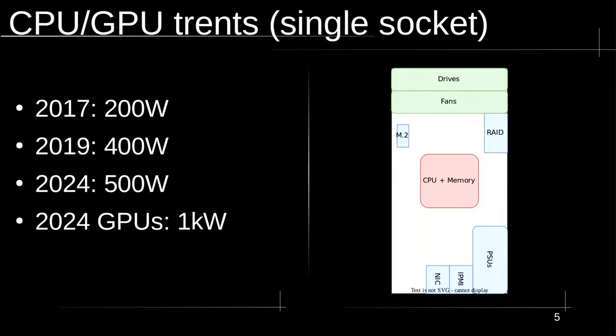The power usage of CPUs over the past few years has been going up and up. In 2017, the servers we bought were 200 watts; 2019, 400 watts; and in 2024, the latest generation announced is 500 watts. It still has to fit in the same chassis, so cooling gets a lot more complicated. On the GPU side, the latest NVIDIA GPUs are rated at one kilowatt each — put eight in a server and you're at eight kilowatts. Cooling that is non-trivial, and getting power to that is also non-trivial.